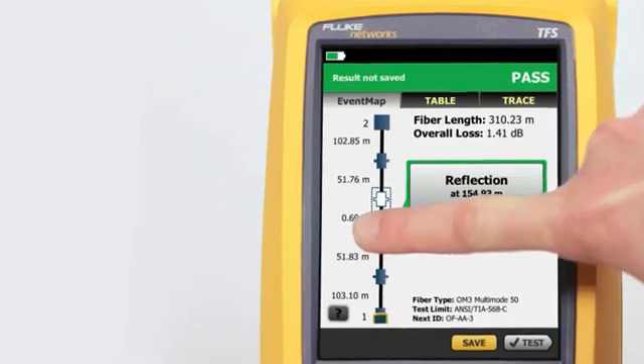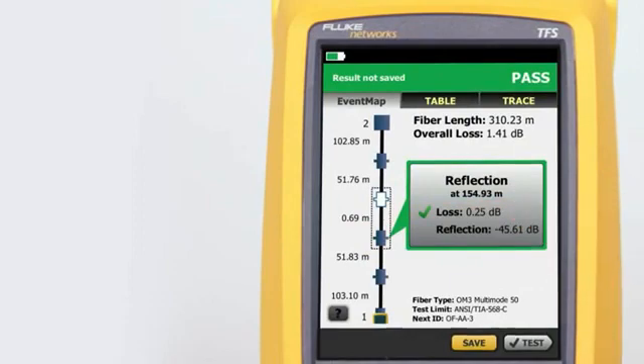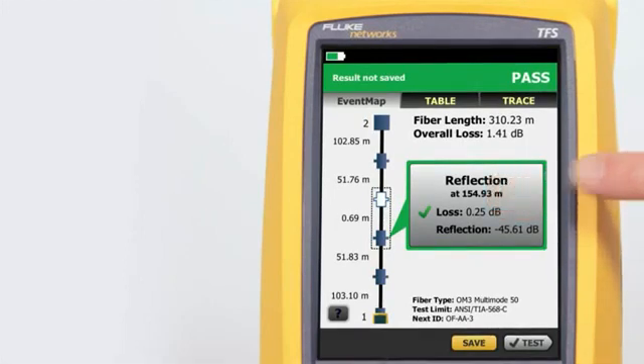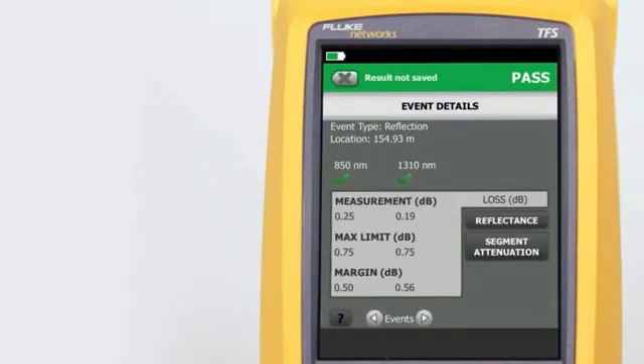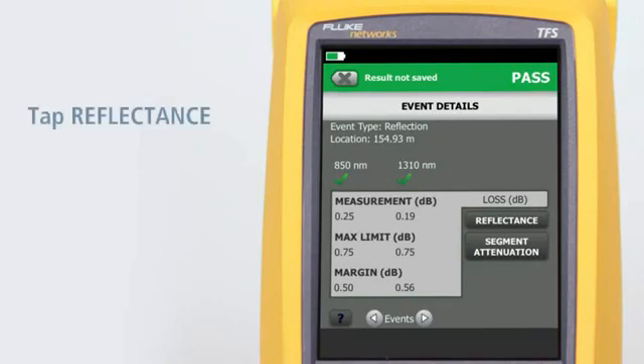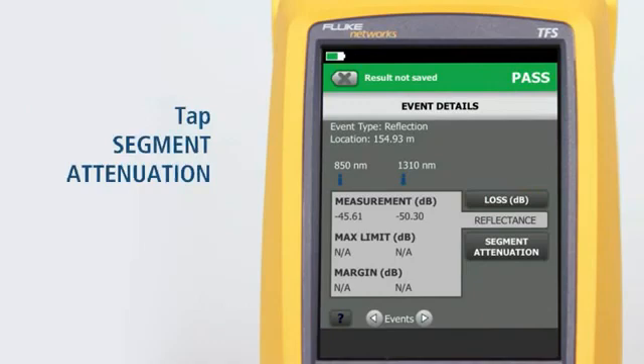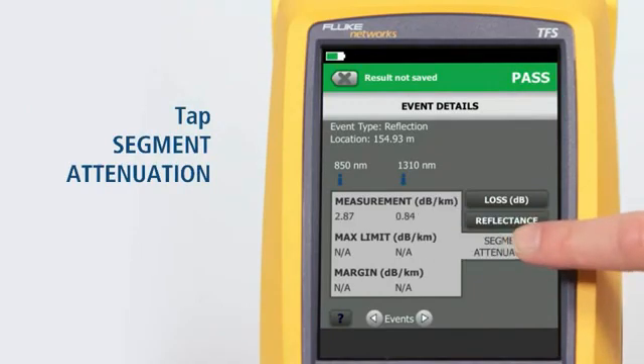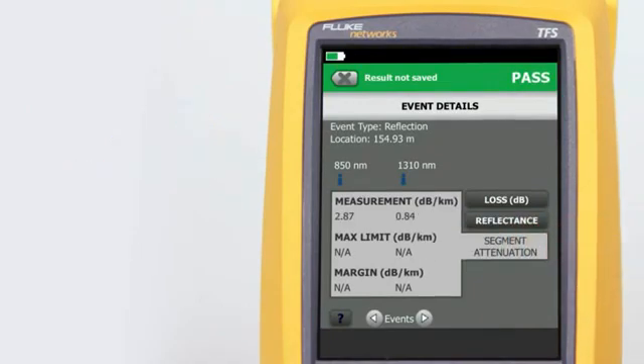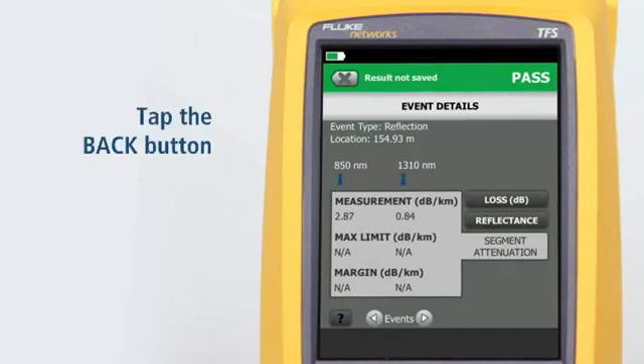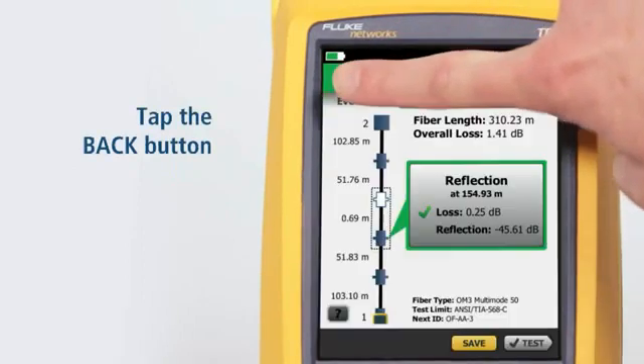By tapping on any of the color-coded icons — red or green for pass/fail — we can view the event's summary information. We can view any event's details by tapping its summary information bubble. The event's loss measurement and margin details are shown first. Tapping Reflectance allows us to view the reflection measurements, and tapping Segment Attenuation shows the measurement of the fiber segment prior to the event. Tapping the Back button takes us back to the Event Map.